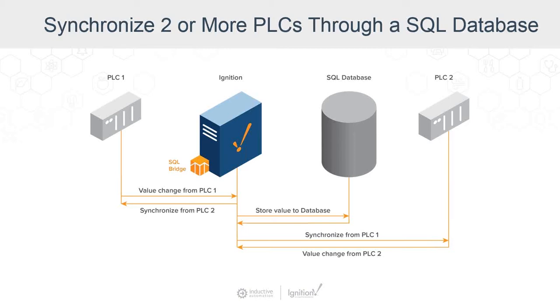We have many different modes for conflict resolution — determining whether the database or the PLCs win if we restart the system or lose communication. There are a lot of applications where you have isolated islands of PLCs not connected in a larger control system, and it could be costly to add a controller in the middle to connect them all. With Ignition, we can use the SQL Bridge module and transaction groups to perform synchronization or move data around, triggering when values change.